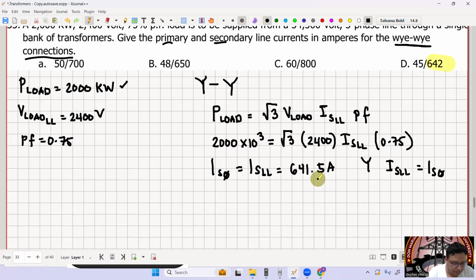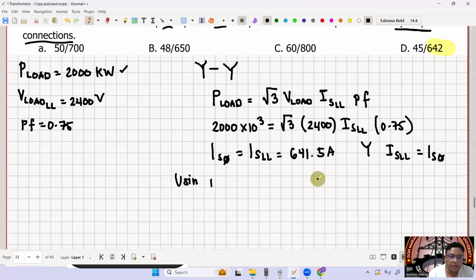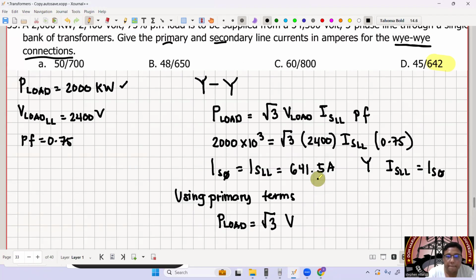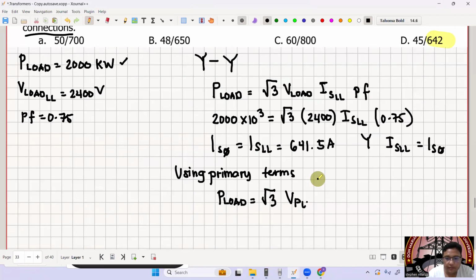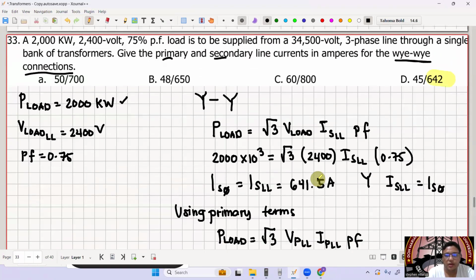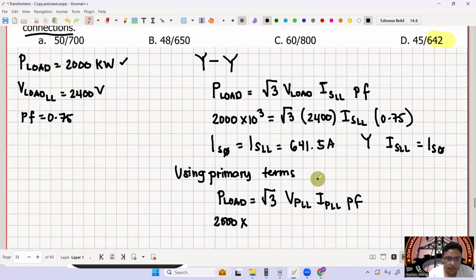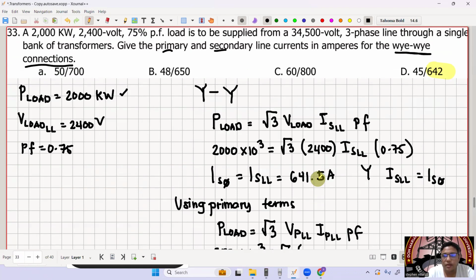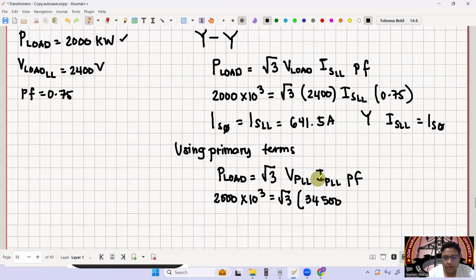So using primary terms, yung ating P load is equal to square root of 3 ng ating VP line to line times yung ating IP line to line times yung ating power factor. So this is now 2,000 times 10 raised to 3 is equal to square root of 3 multiplied by 34,500 multiplied by your IP line to line times yung ating power factor na 0.75.